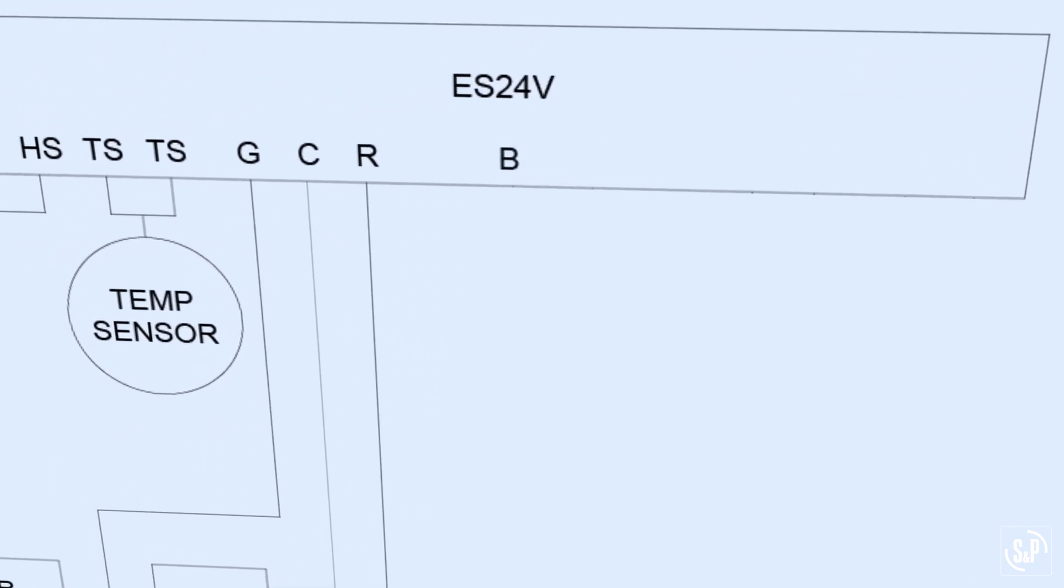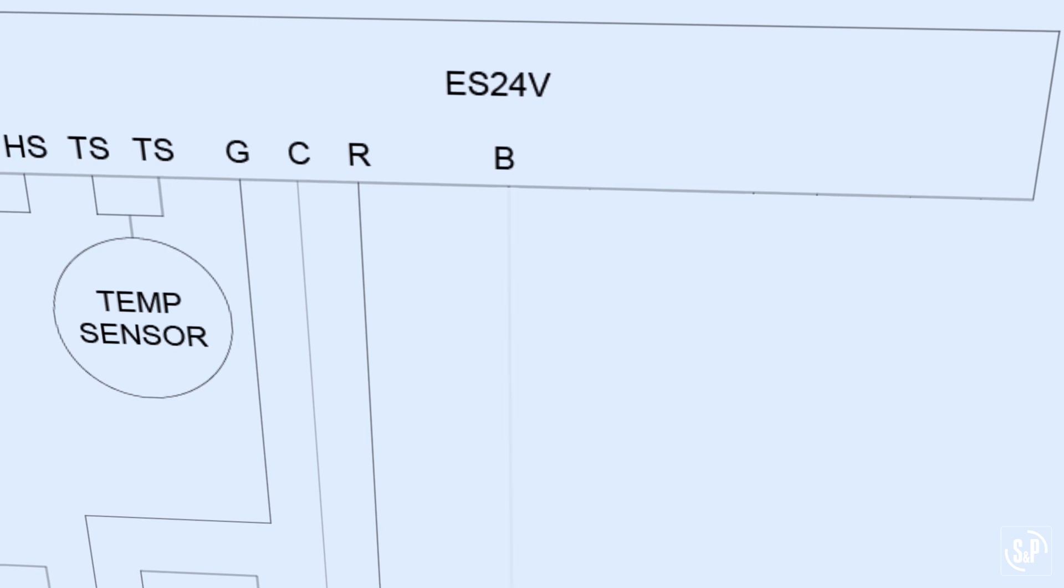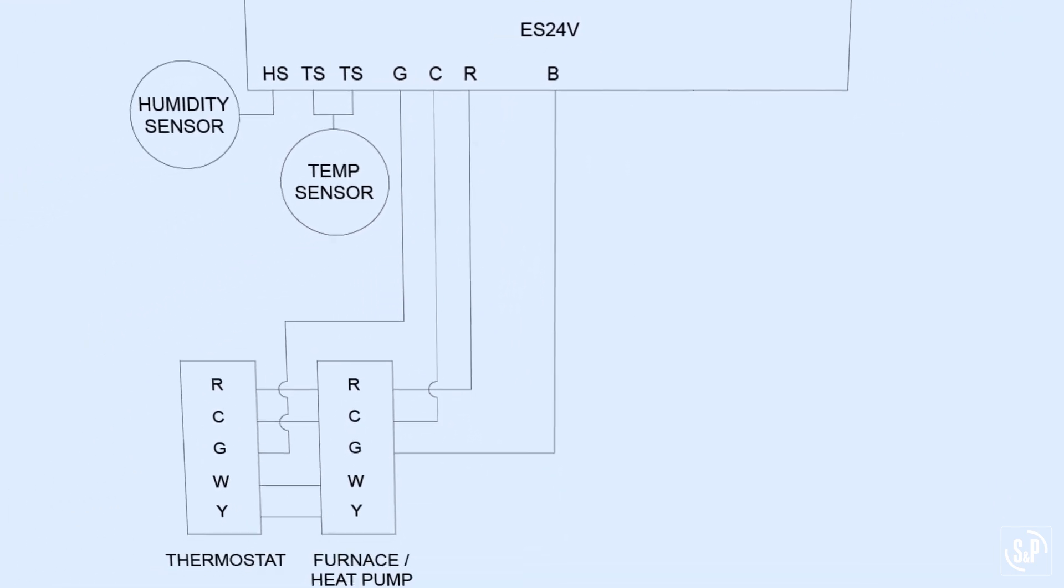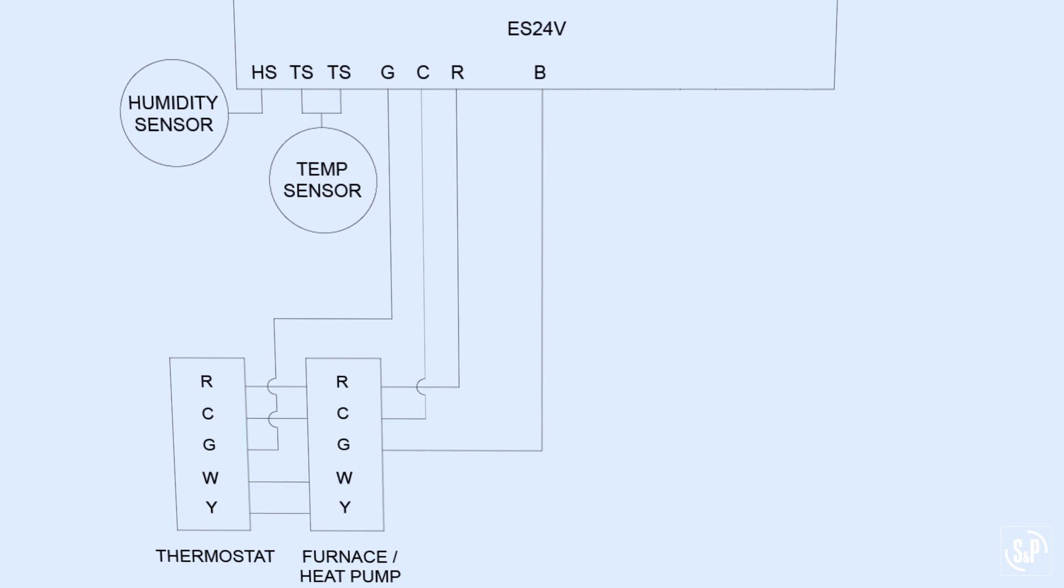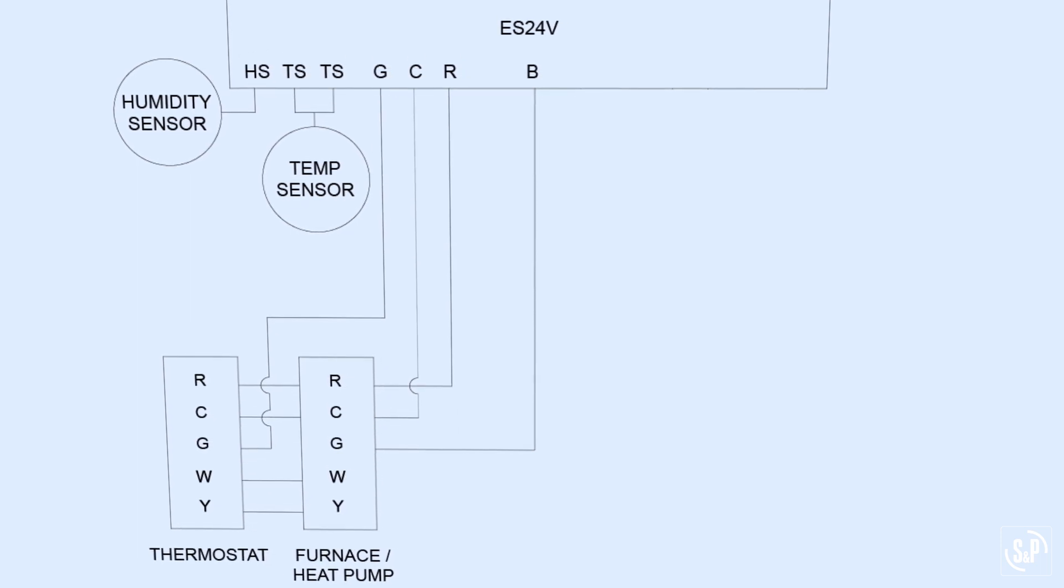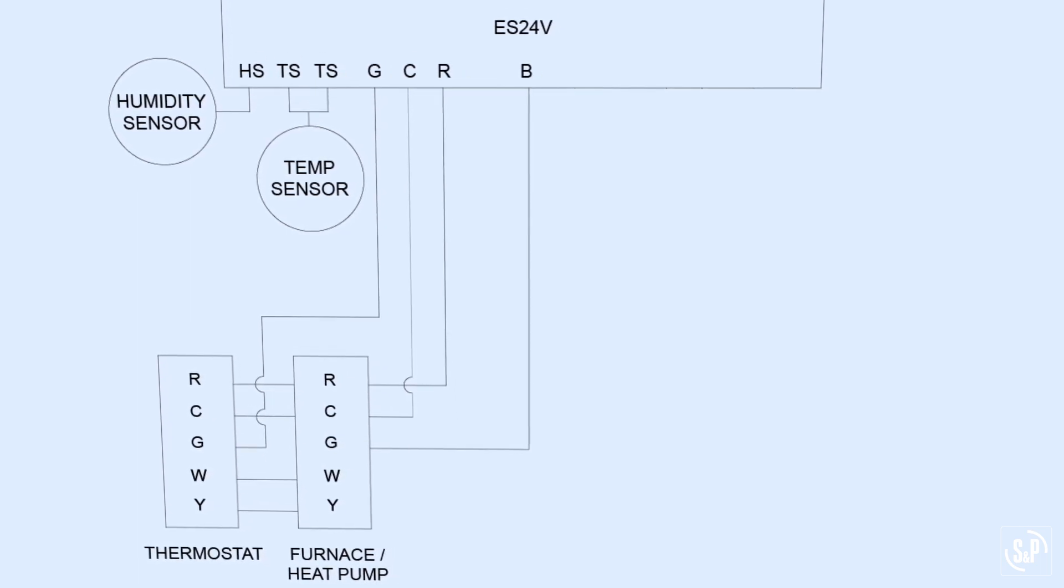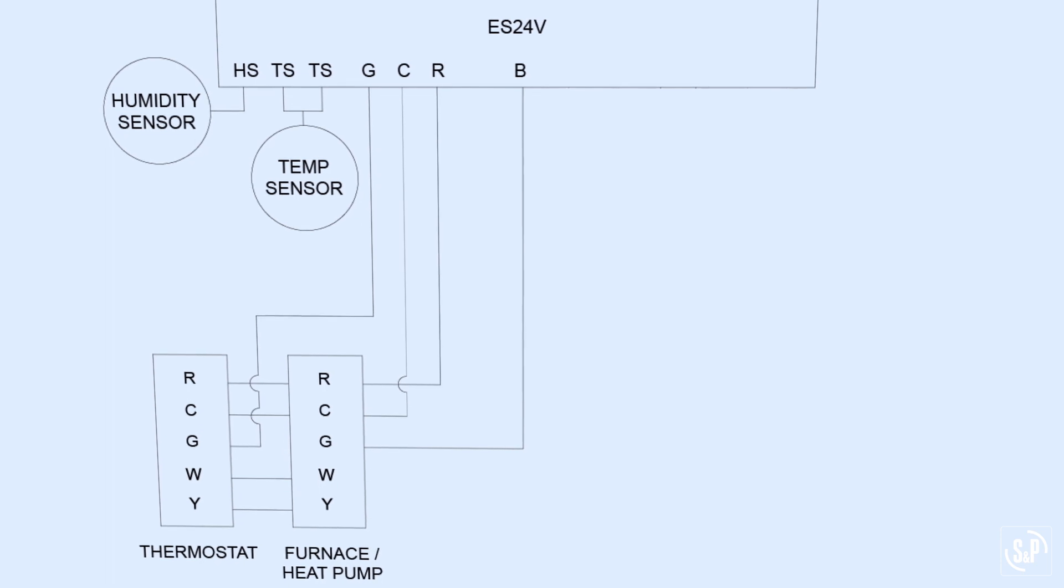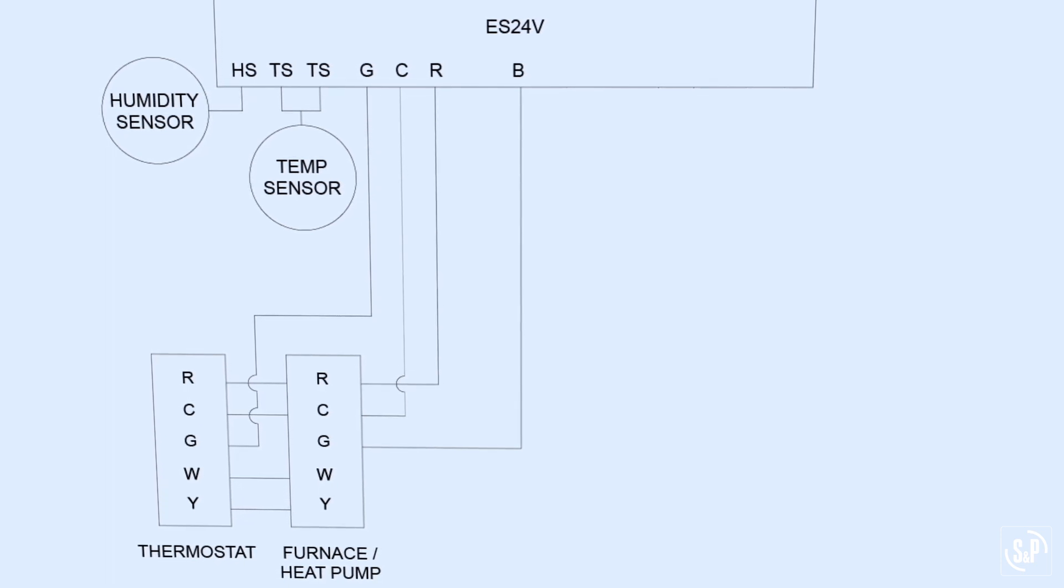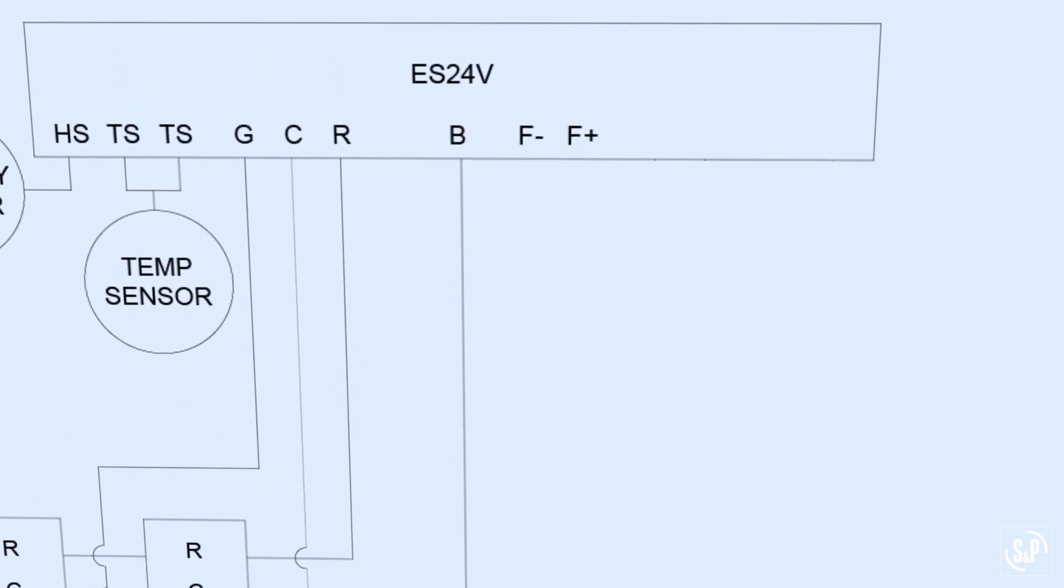The B terminal is the air handler unit output and connects the ES24V B terminal to HVAC unit G. This connection allows the thermostat to communicate to the air handler unit regularly and allows the ES24V to command the HVAC fan to help distribute the fresh air through the existing ductwork as necessary.